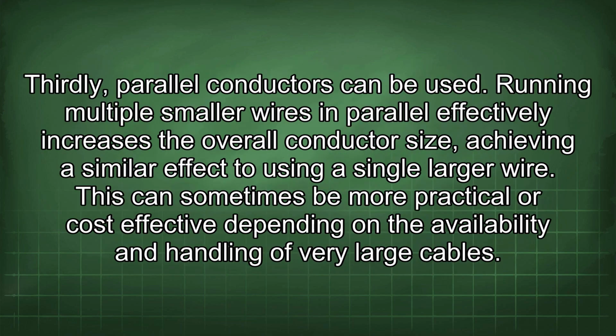Thirdly, parallel conductors can be used. Running multiple smaller wires in parallel effectively increases the overall conductor size, achieving a similar effect to using a single larger wire. This can sometimes be more practical or cost-effective depending on the availability and handling of very large cables.